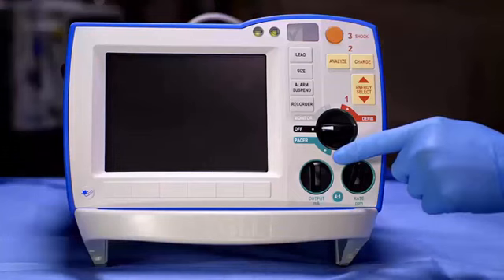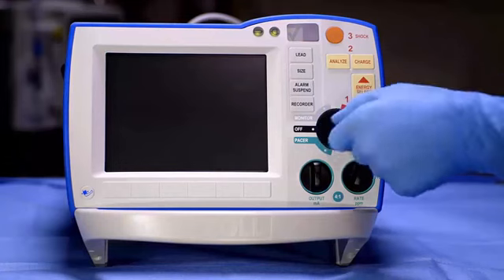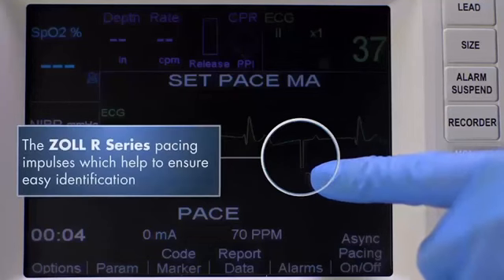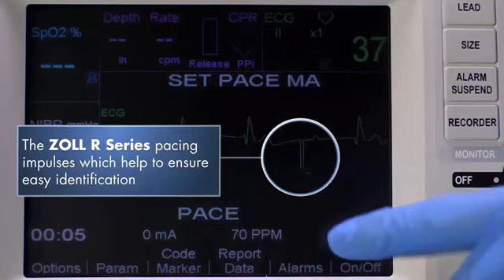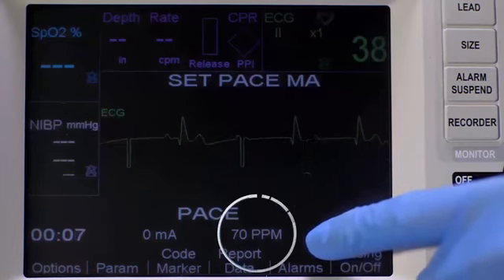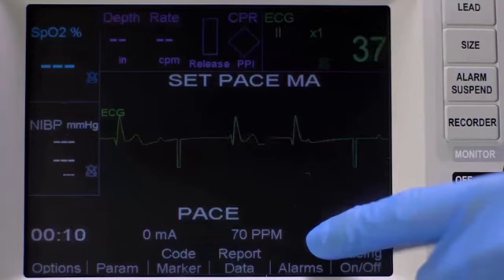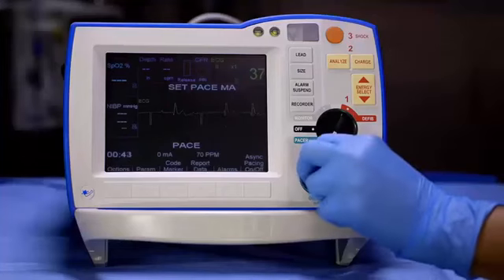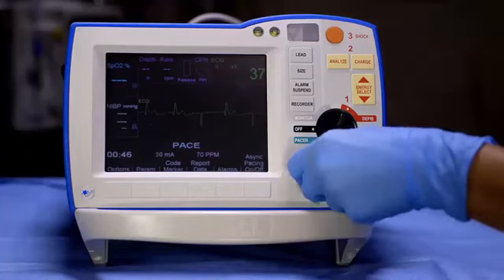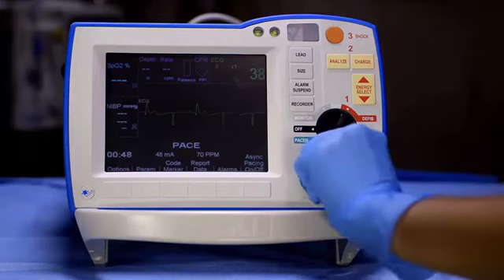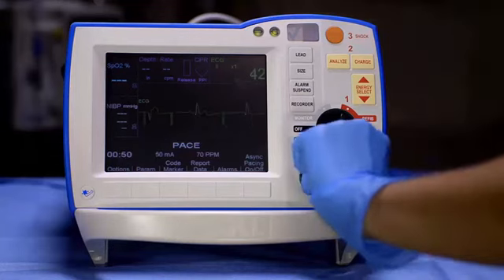To begin pacing your patient, turn the dial to pacer. The downward spikes indicate pacing pulses. The rate will default to 70 pulses per minute unless your institution has configured it otherwise. Next, increase the output by turning the dial clockwise. Normal range for capture is between 40 and 80 milliamps.